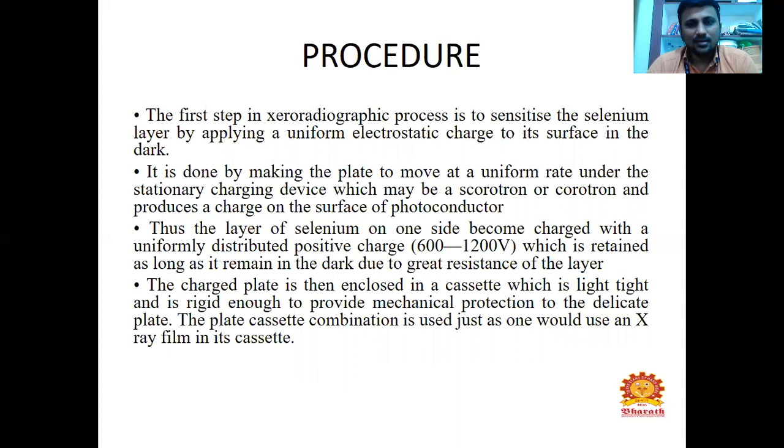Thus, the layer of selenium becomes charged with a uniformly distributed positive charge, which is retained as long as it remains dark, due to the great resistance of the layer. The charged plate is then enclosed in a cassette, which is light-tight and rigid to provide mechanical protection to the plate. The plate and cassette combination is used just as one would use an X-ray film in a cassette.